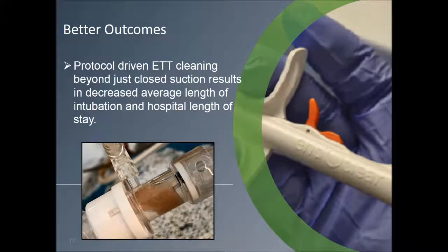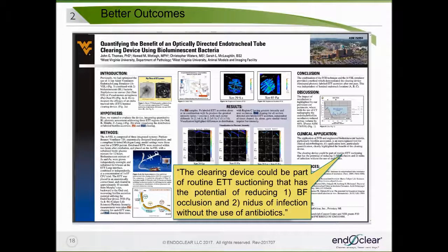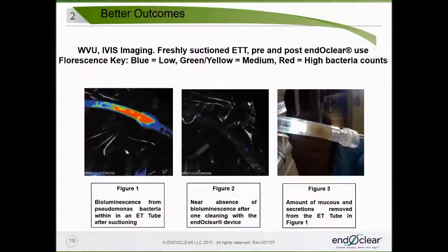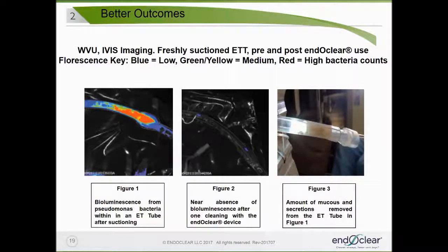Now that we understand the ubiquitous nature of the problem and the inadequacy of closed suction to maintain artificial airways at their lowest work of breathing, let's look at why addressing this problem effectively results in improved patient outcomes. This study out of West Virginia University suggested that clearing the endotracheal tube could be an adjunct to closed suctioning and could both reduce endotracheal tube occlusion and minimize colonization. The furthest left photo is of an endotracheal tube from an in vitro patient ventilator model in which the biofilm was created using bioluminescent Pseudomonas aeruginosa. The middle photo is of the endotracheal tube following one cleaning pass with an ENDOCLEAR device. The last photo on the right shows the amount of secretions that were obtained with one pass of the ENDOCLEAR device and that were not removed by closed suction.